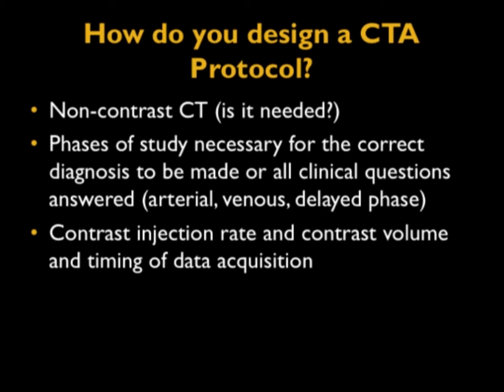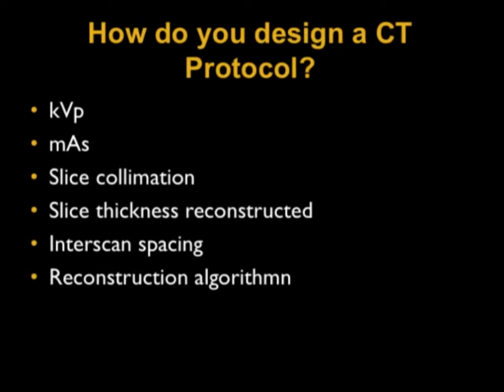You also need to know, when making protocols, what kind of contrast you're going to give — the volume, the timing, and delivery. You also need to know the parameters of your scanners. You have to make a protocol that's specific for each machine. If you have three different scanners, you need three different protocols. They will vary in KVP and MAS, slice collimation, slice thickness reconstructed, and scan spacing. We like 0.75 by 0.5, but everything from reconstruction algorithms will be variable depending on the scanner.